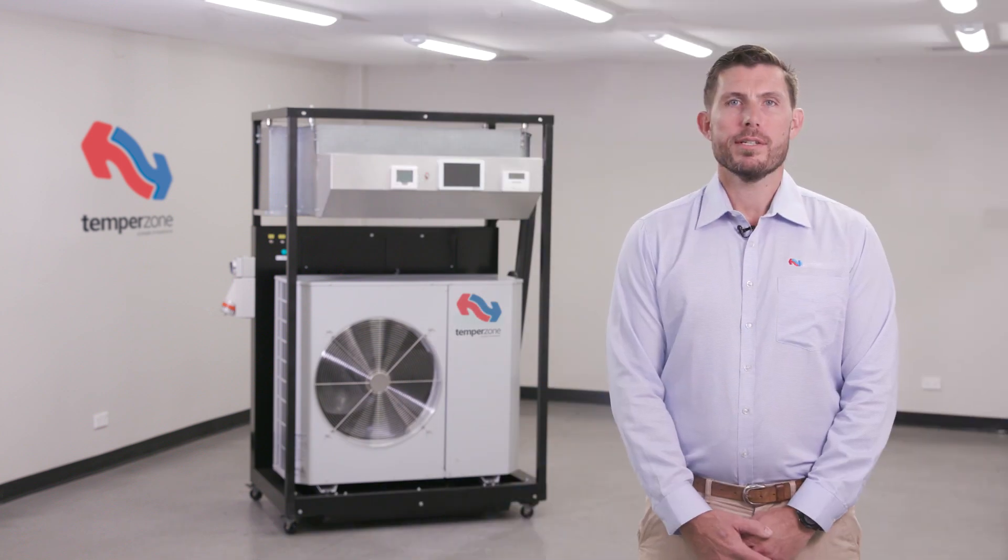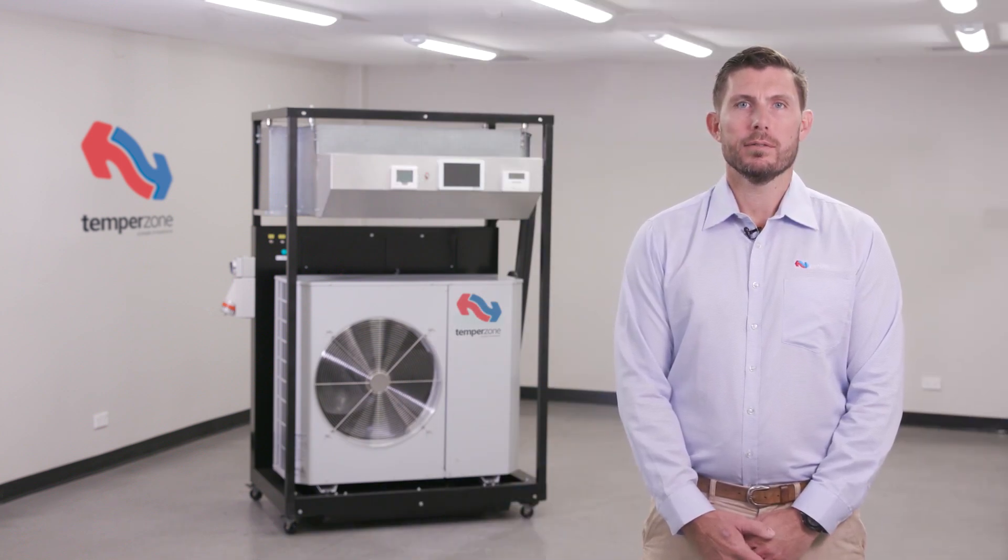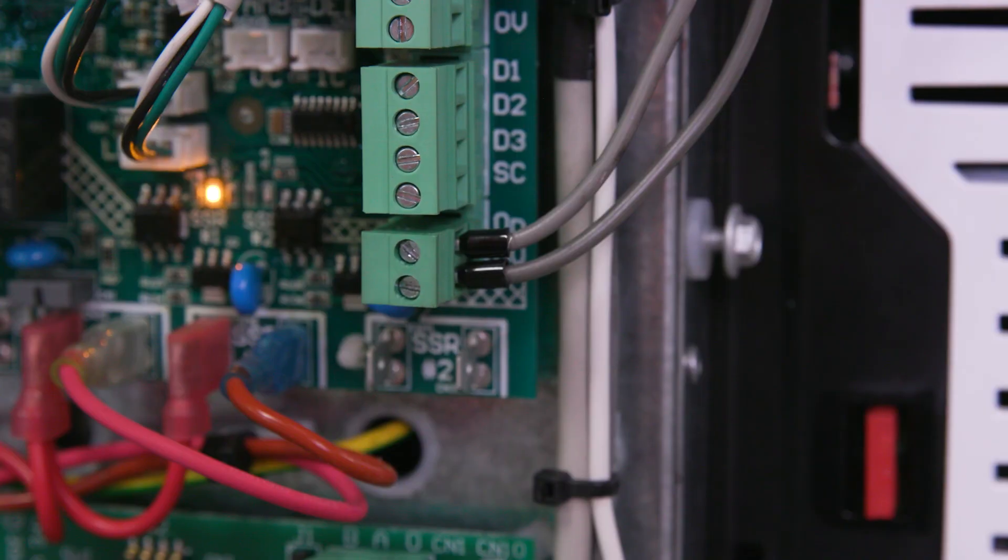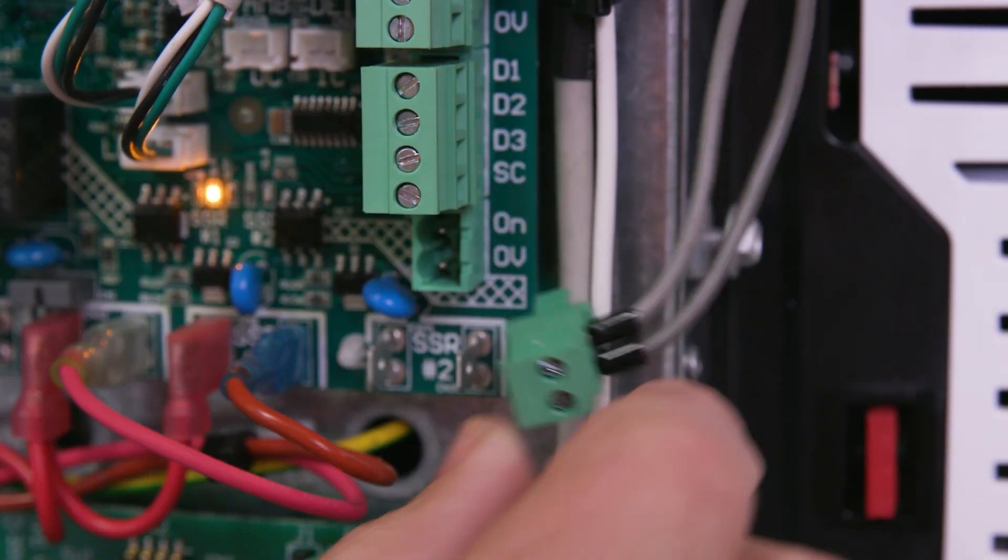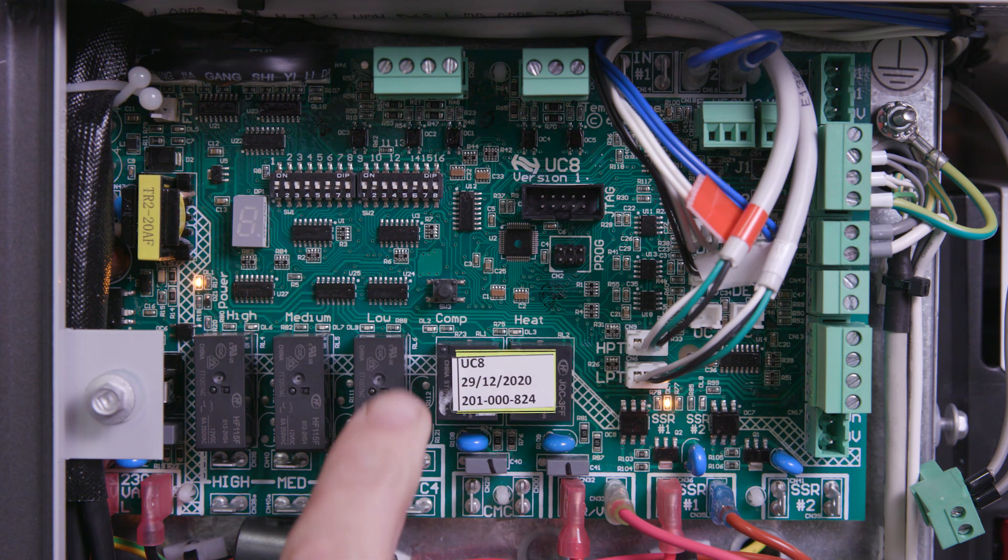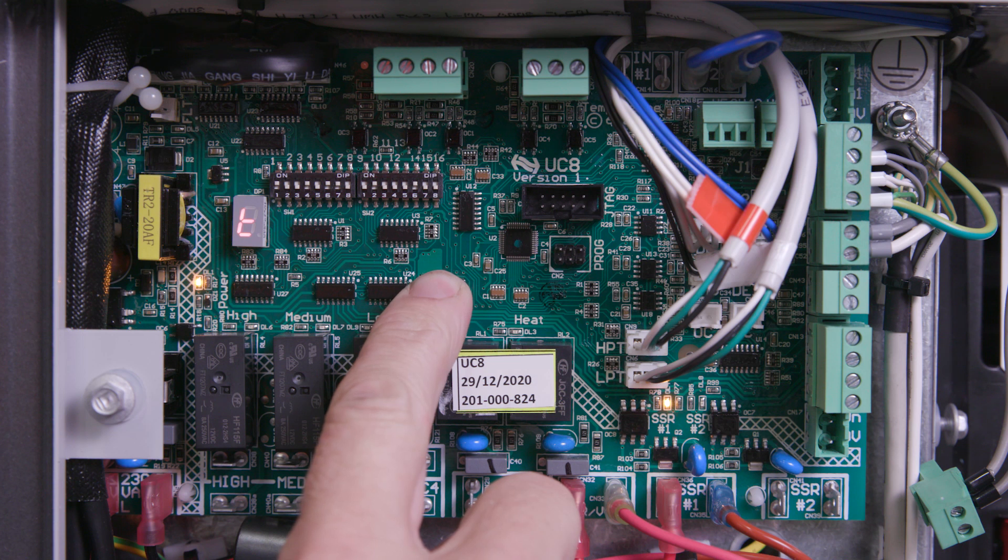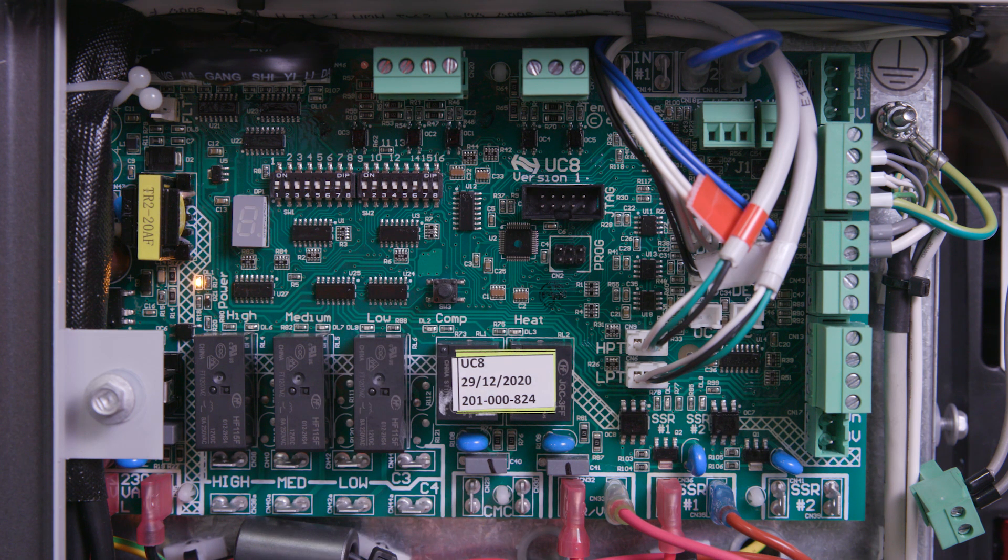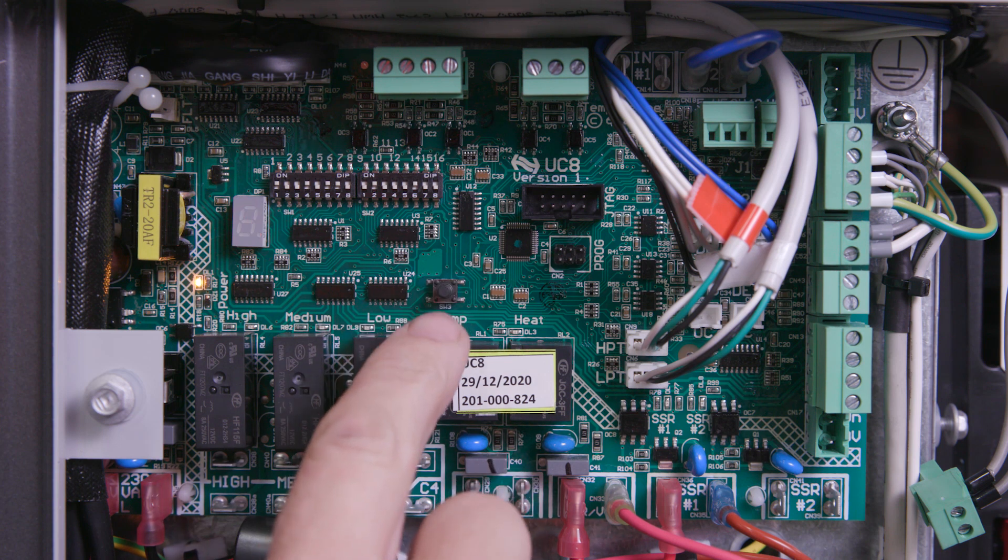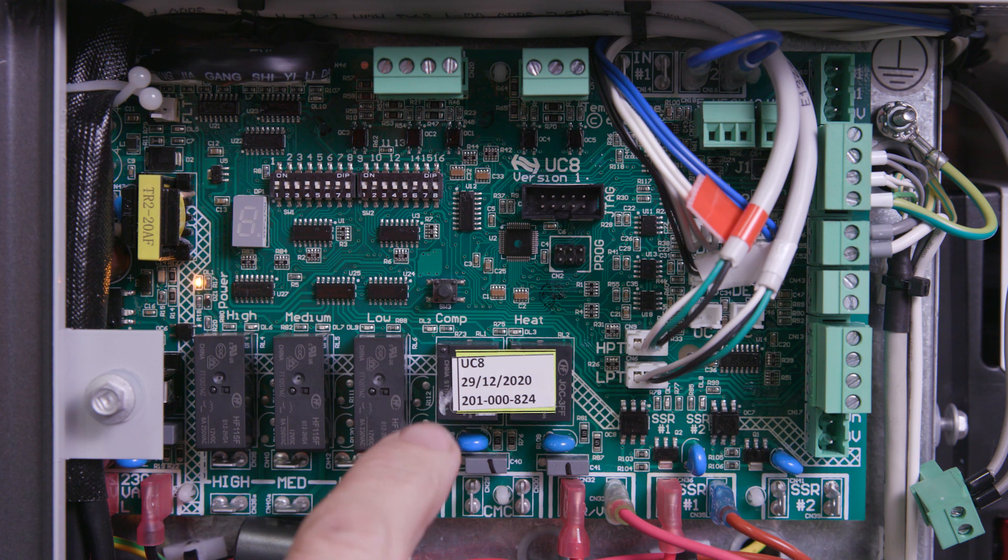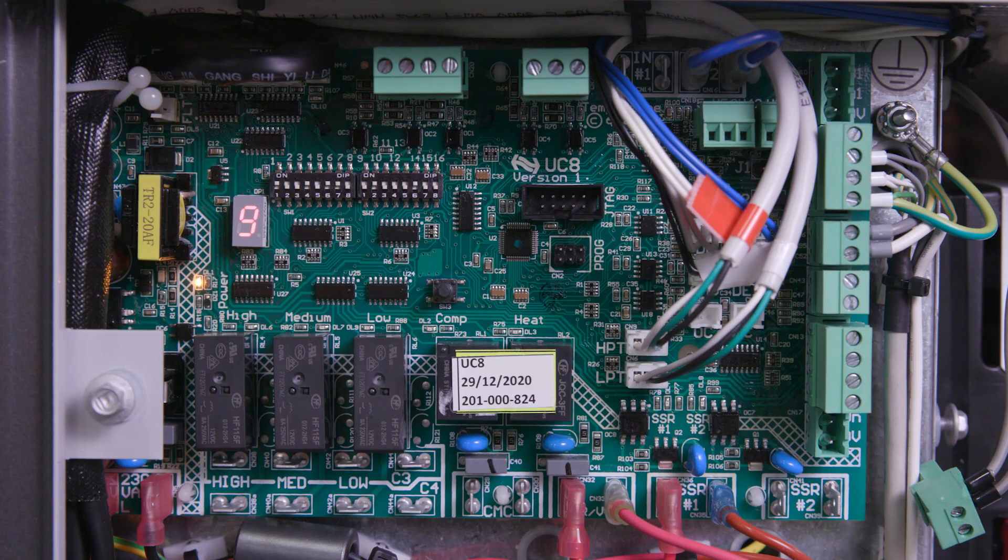Version 6 to version 6.13 has four levels of special mode. First remove the remote on-off terminal. Level 1 can be accessed by pressing and holding the SW3 push button until reaching the desired special mode. Release the push button and the UC8 will enter the special mode settings. Single taps allow adjustments to be made. Adjustments are saved by not touching the SW3 push button for 15 seconds. The UC8 will then return to the main menu.